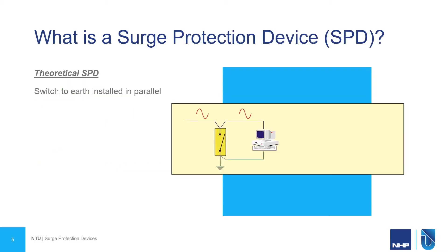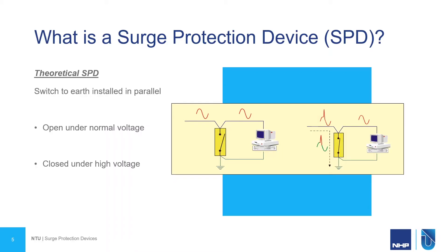So let's take a look at the operation of an SPD. In the ideal world, an SPD would simply be a switch to earth that is installed in parallel with the sensitive load. Under normal conditions, that switch would be open, so the mains voltage would be seen by our equipment. Then under surge events, when the SPD sees a high voltage, it closes that switch and conducts that spike in energy down to earth, and all our sensitive equipment sees is the mains voltage.